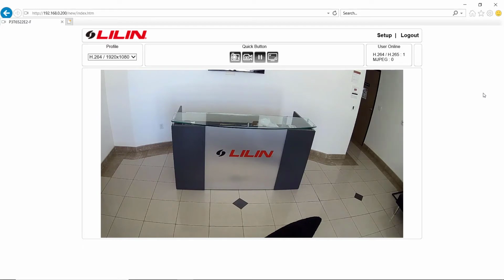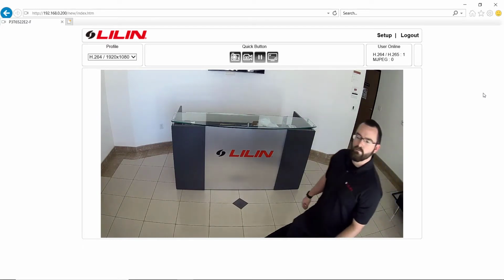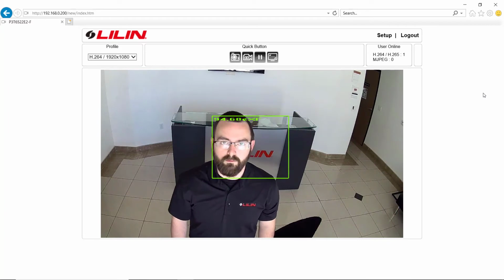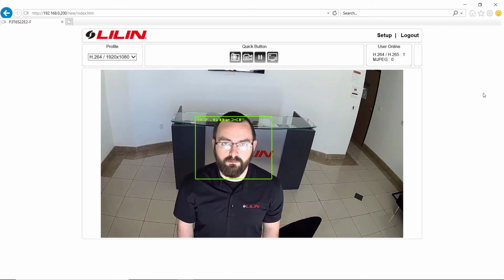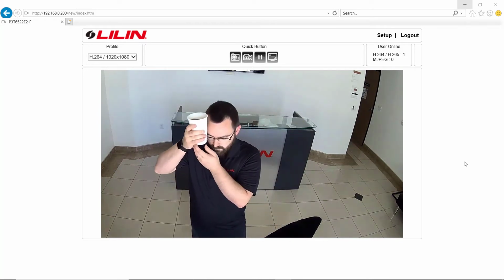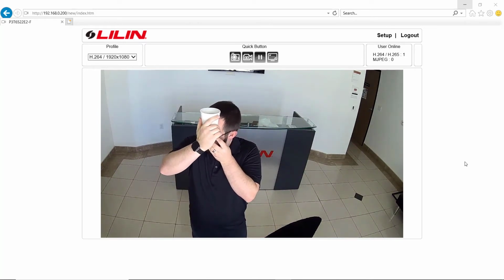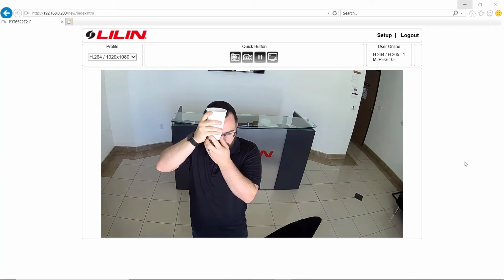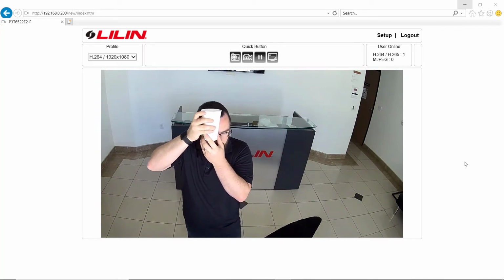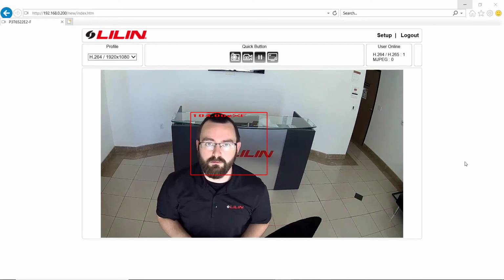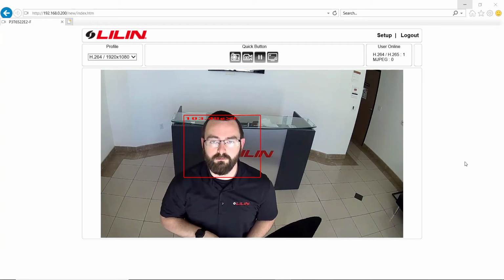So here we can see the camera's web interface, and I'm using this camera as a standalone unit. So I enter the frame, I stand still for about 3 to 5 seconds to allow the camera to get a good read, and then I exit the frame. In order to simulate what would happen if a person with an elevated temperature enters the frame, I go ahead and use my hot coffee cup here to heat up the temperature of the surface skin on my face, and then I stand in front of the camera and you can see that it is now reading an elevated temperature.